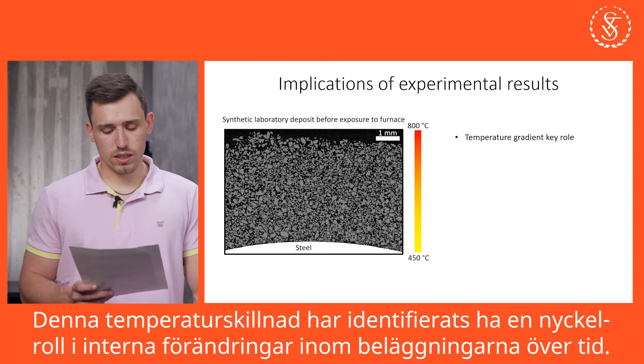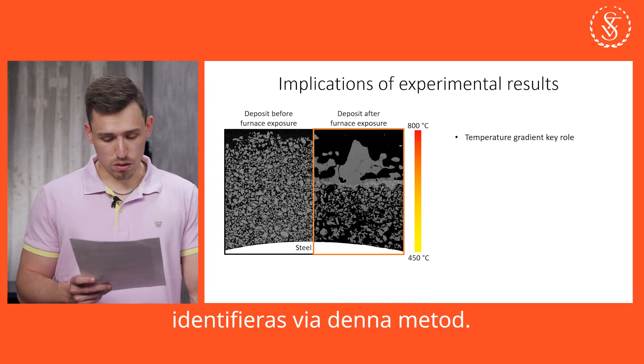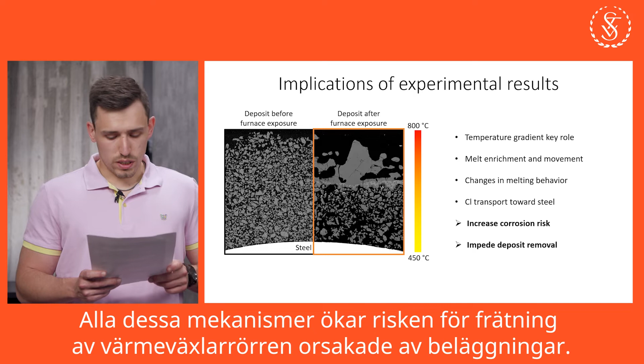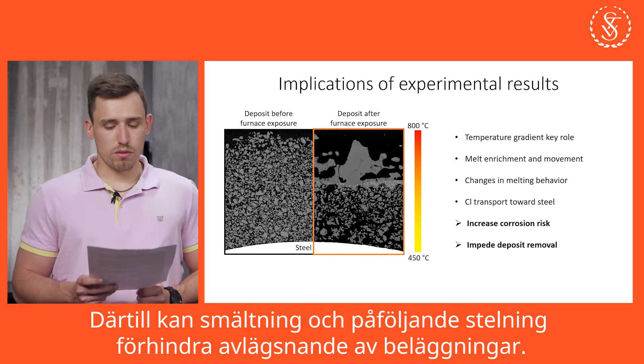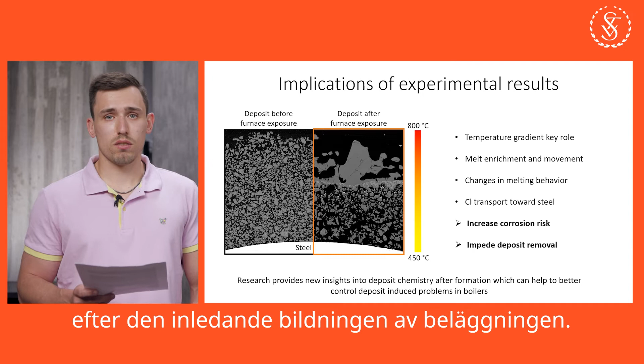Several mechanisms are responsible for changes within this deposit that alter the morphology and chemistry within a deposit over time. Enrichment of corrosive elements in the molten phase can result in local changes of the deposit's melting behavior, and this melt can also move towards the steel. Furthermore, gas phase transport of alkali chloride towards the steel could be identified. All these mechanisms increase the risk for deposit-induced corrosion, and in addition, melting and subsequent solidification of the deposit can impede deposit removal. The goal of my research project is to provide new insights into these mechanisms that take place over time after the initial deposit formation took place.